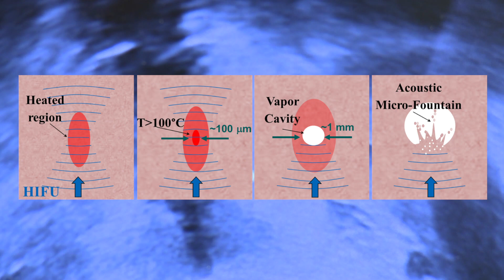Our team is developing a technology. We termed it boiling histotripsy, or BH technology, and the aim is to mechanically liquefy tissue rather than thermally ablate it at the focus. We use millisecond-long pulses with very high amplitude that are focused, and while propagating from the transducer to the focus, initially harmonic waves transform to the shock wave at the focus. And these shock waves heat tissue to very high temperatures within each pulse. Then a vapor bubble forms, and interaction of shock waves with this bubble results in tissue disintegration to subcellular debris through the mechanism of atomization and acoustic fountain.